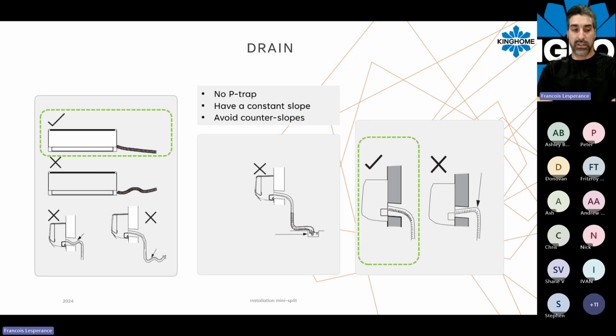for too long, and that can create some issues, because all the dust and dirt coming in from the filter or on the coil will be mixed with water, which will create some kind of slime that will eventually block the drain pipe somewhere. So it needs to have a constant slope, be as clean as possible, and as dry as possible when it's not in use. If you have any kind of wiggling like this on your drain pipe, that can cause some water overflow from the head, causing damage and issues for your customer. So make sure the drain is correct and you have tested it properly.